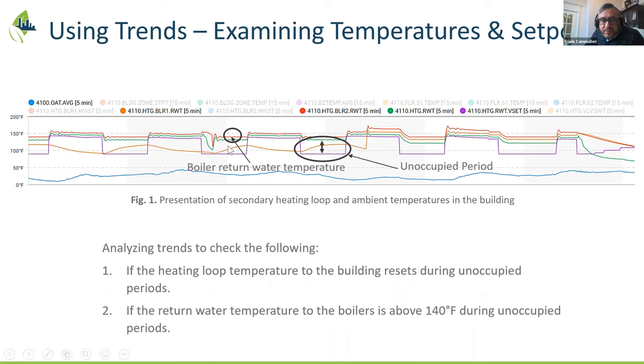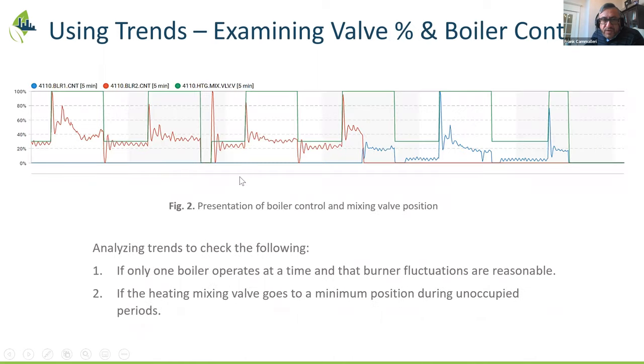Wanted to give you a taste of that, but also want to give you a taste for other types of analysis. In this case, same building, but a different part of the sequence we're testing. We want to make sure we're investigating trends to confirm only one boiler operates at a time and that burner fluctuations are reasonable.